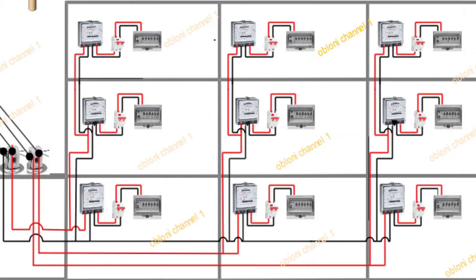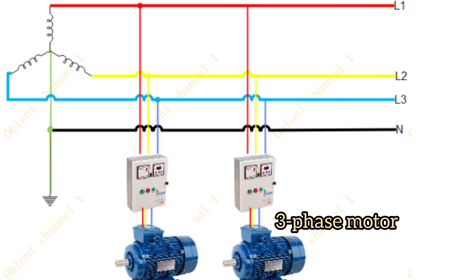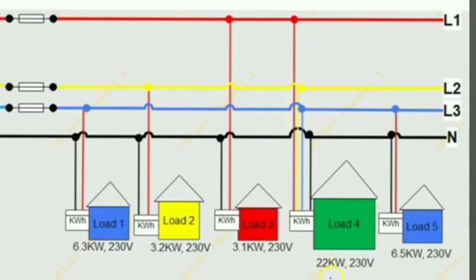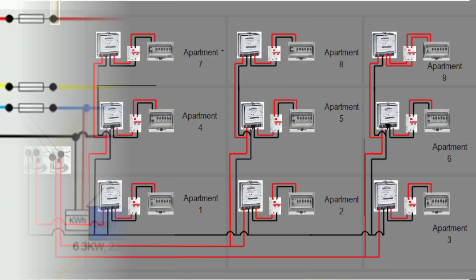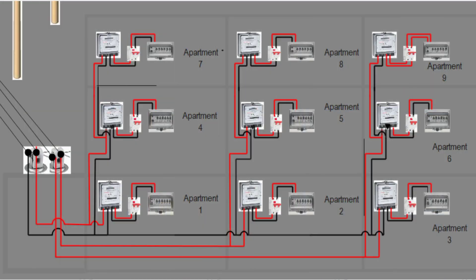There are two major reasons why you would need to do that. The first reason is when you have a wiring that involves three-phase equipment — equipment that requires three lines to work. The other instance is where all the loads you have are single-phase loads, but you have a very large number of them. Adding up their total consumption, you will have a very large power requirement, and so in that case you will also need to bring in all three phases and distribute the power appropriately to the various loads.